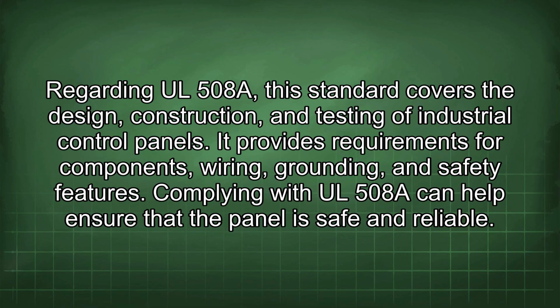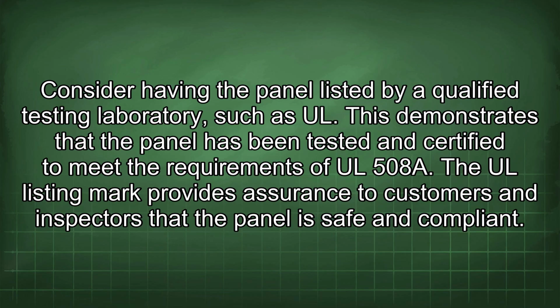Regarding UL 508A, this standard covers the design, construction, and testing of industrial control panels. It provides requirements for components, wiring, grounding, and safety features. Complying with UL 508A can help ensure that the panel is safe and reliable. Consider having the panel listed by a qualified testing laboratory, such as UL. This demonstrates that the panel has been tested and certified to meet the requirements of UL 508A. The UL listing mark provides assurance to customers and inspectors that the panel is safe and compliant.